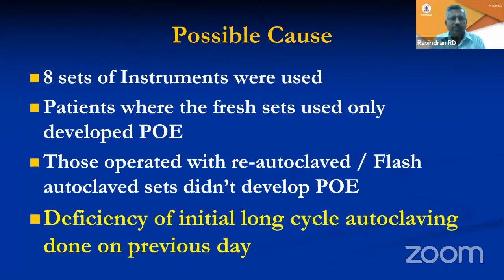Then the 5th case was operated with a set of the same instruments, but they were autoclaved. They underwent flash autoclaving, and it was the same trolley. The trolley was not changed, only the instruments were autoclaved and brought back, and they were used. And that particular patient did not develop it. Then subsequently, the next 4 cases were operated with the instruments that were meant for SICS. So there was some deficiency in the long cycle autoclaving that was done on the previous day. So that was the clue.